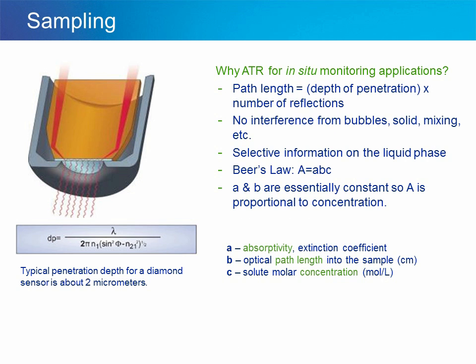Why attenuated total reflectance for in-situ monitoring applications? The path length is equal to the depth of penetration times the number of reflections on the sensor. You will observe no interference from bubbles, solids, or mixing, and you'll get selective information on the liquid phase in the spectrum. The spectrum will conform to Beer's Law: absorbance equals the product of the molar absorptivity, path length, and concentration. Since molar absorptivity and path length are essentially constant, absorbance is proportional to concentration. Penetration depth is a function of the wavelength of the radiation, the refractive indices of the sensor and liquid, and the angle at which radiation impinges on the sensor. A typical penetration depth for a diamond sensor is about 2 micrometers.